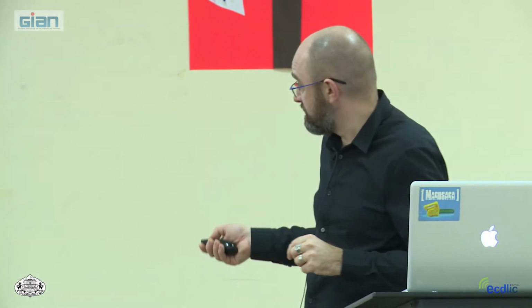You have several lenses here. I will not describe the different lenses. You have the extraction one, which is at minus 10,000 volts. Surely you don't want to touch it, okay? Normally it's disconnected when you open the source. But I know one guy who touched it, and he jumped out from here to the wall, with his hair standing like this. Still alive, huh? Maybe he's not really good in his mind, but he's still alive.